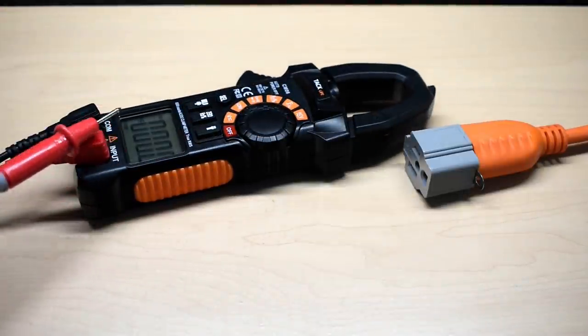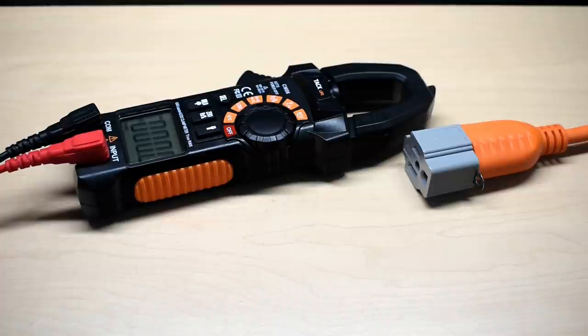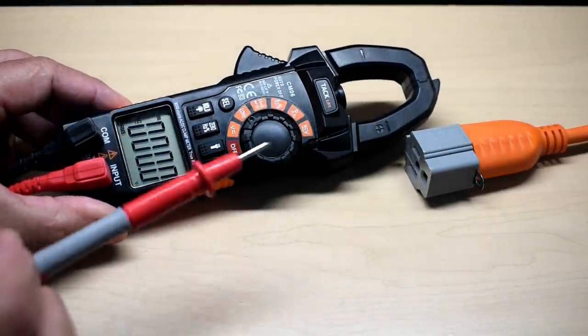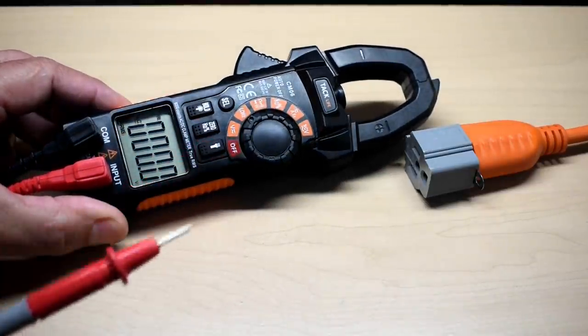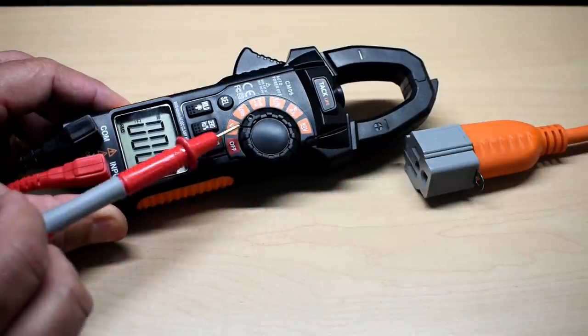You may end up with the reading displayed on the meter of around 120 volts or 220 if that's what you're checking, but the problem is when you plug something into the receptacle it does not power up. What that is is a phantom voltage or a ghost voltage.